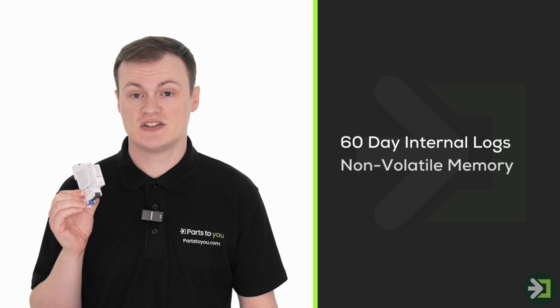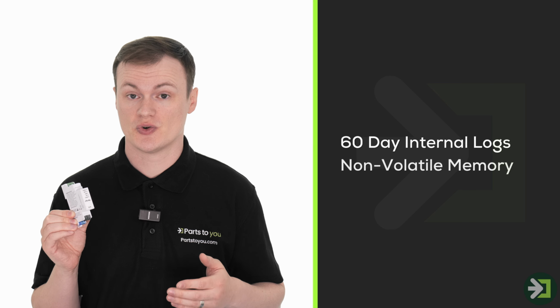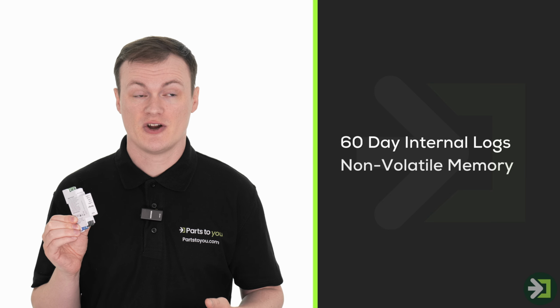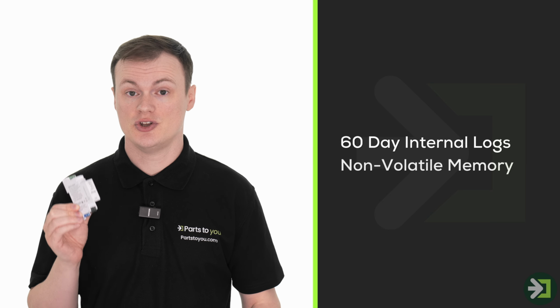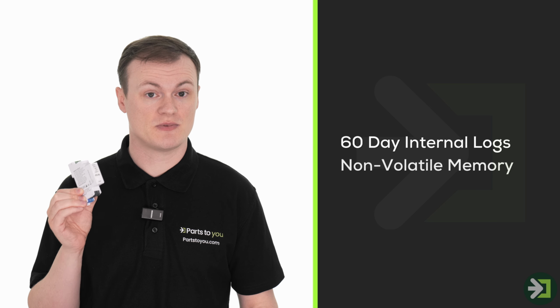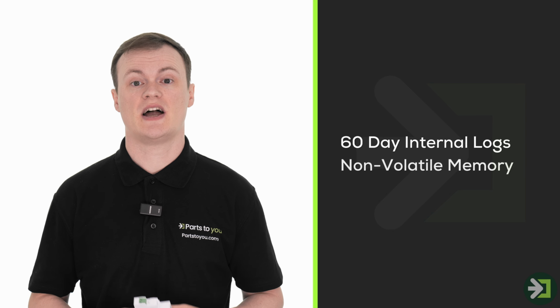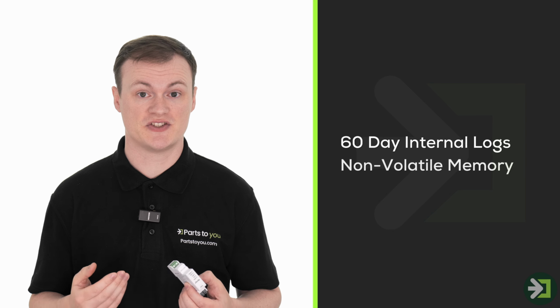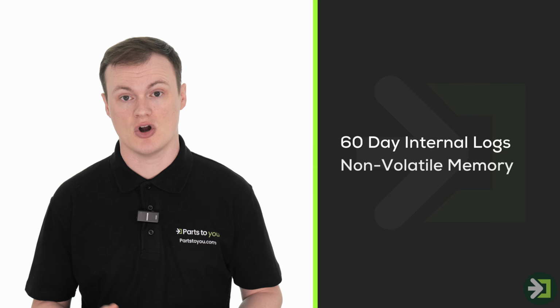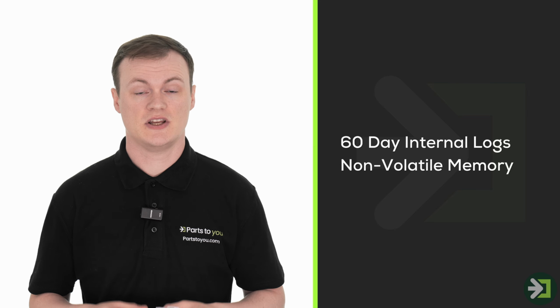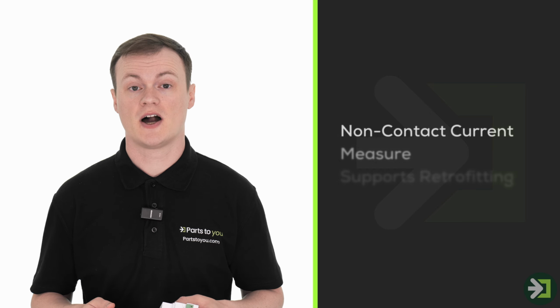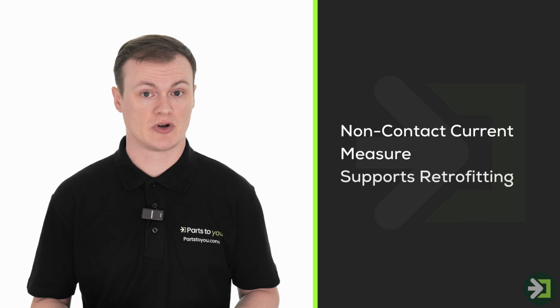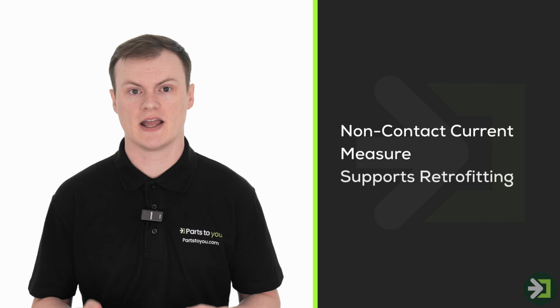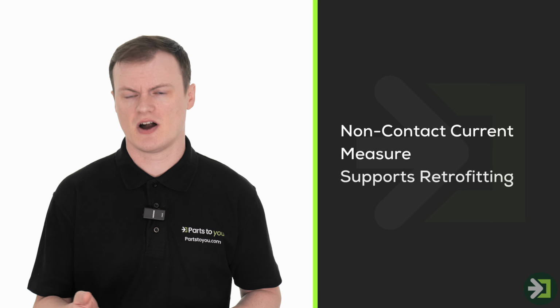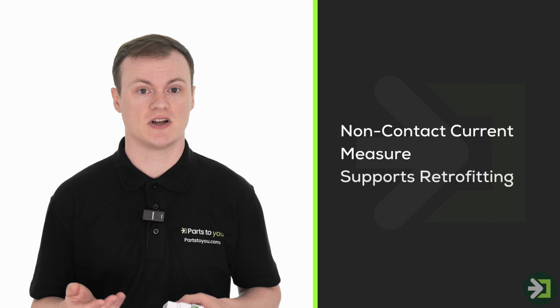The device logs up to 60 days of detailed energy data at 1-minute intervals, stored in non-volatile memory. So even if your network goes down, you will not lose that historical consumption data. That alone puts it ahead of a lot of smart energy systems that forget everything the moment connectivity drops. The included current transformer clamps provide non-invasive measurement, allowing you to monitor circuits without interrupting or modifying existing wiring. It's designed for retrofit and new installations alike.